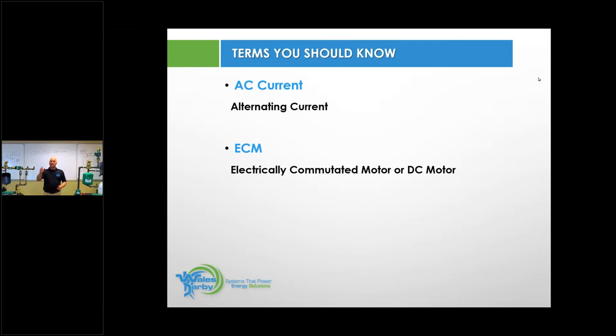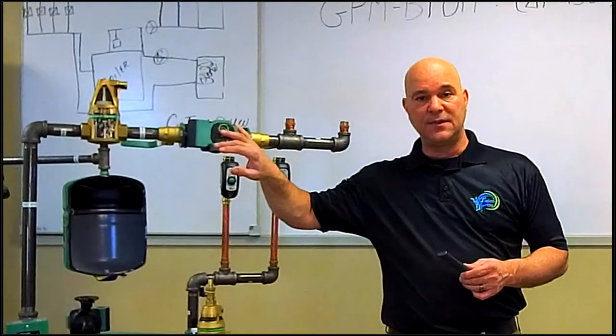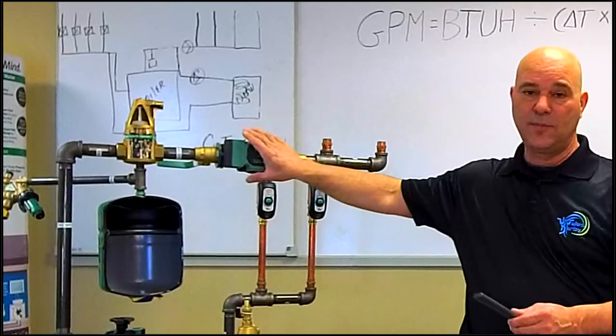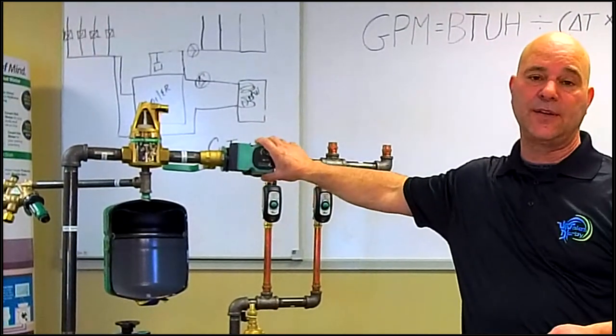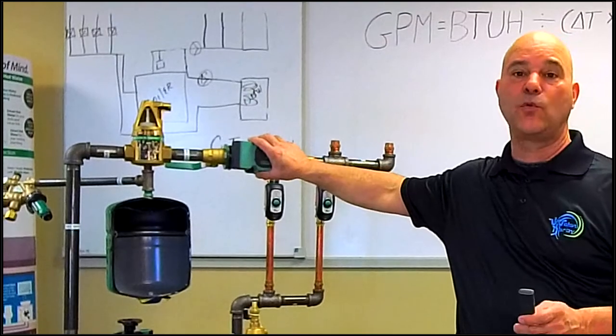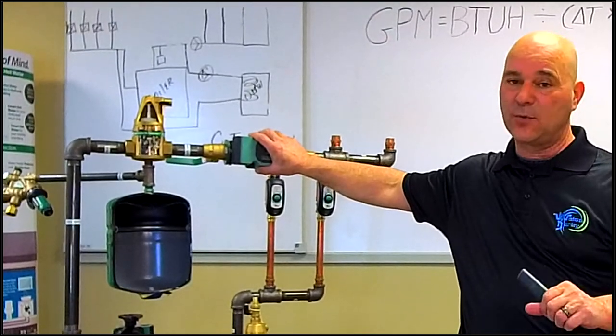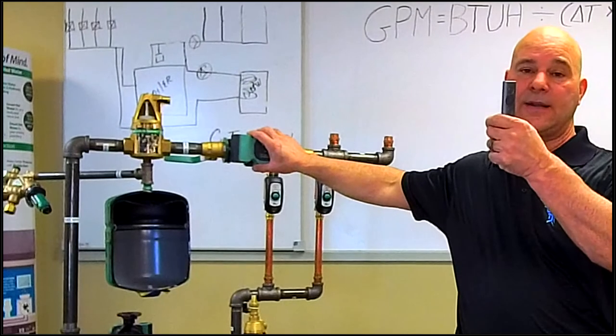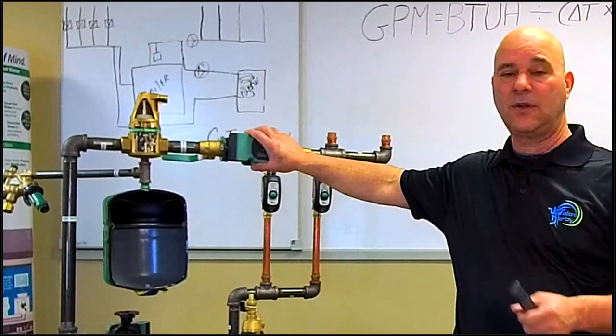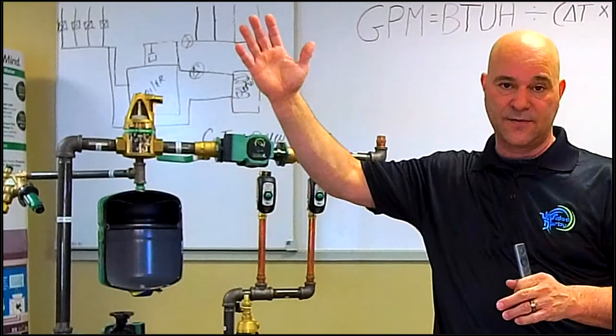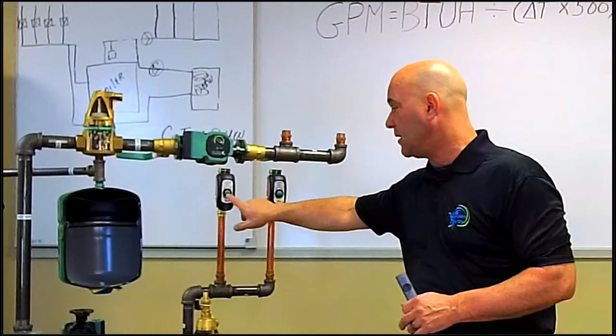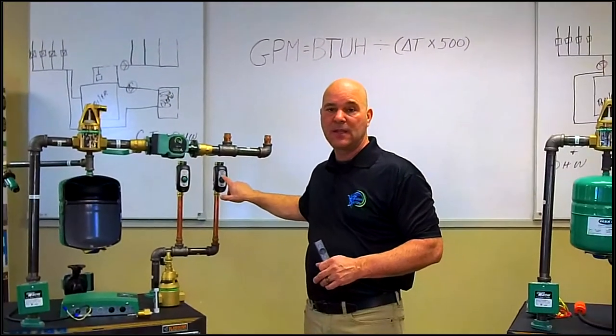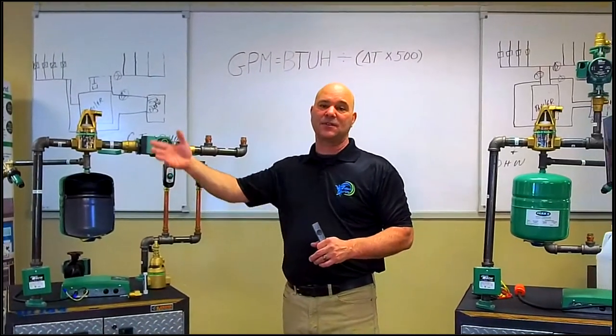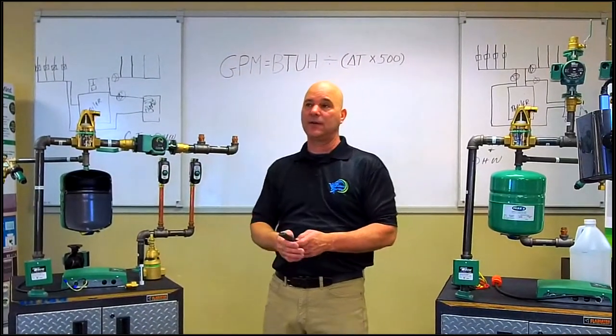ECM, electrically commutated motor. We are DC driven. So this is an ECM motor, DC driven, okay? This will be about 85% more electrically efficient. It will run anywhere from 4 watts to 44 watts of energy. So same run hours, turn that light on, let's call this a light. Now we're looking at anywhere between 4 and 44 watts of energy, depending on how many zones may be calling at any given time. So that's where the electrical efficiency comes in that we were talking about earlier.